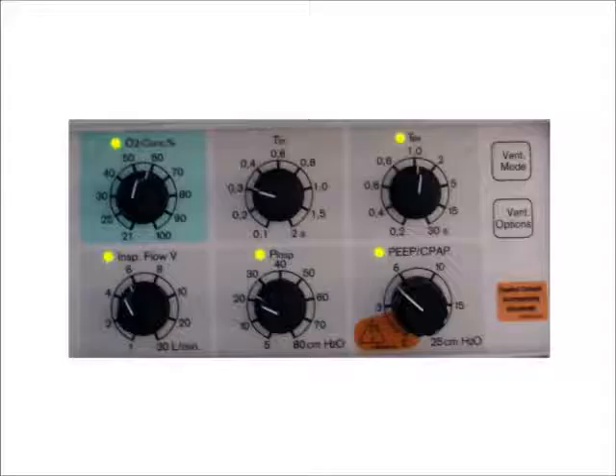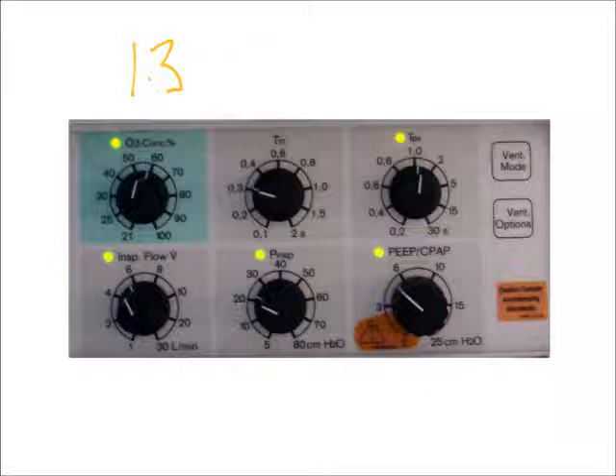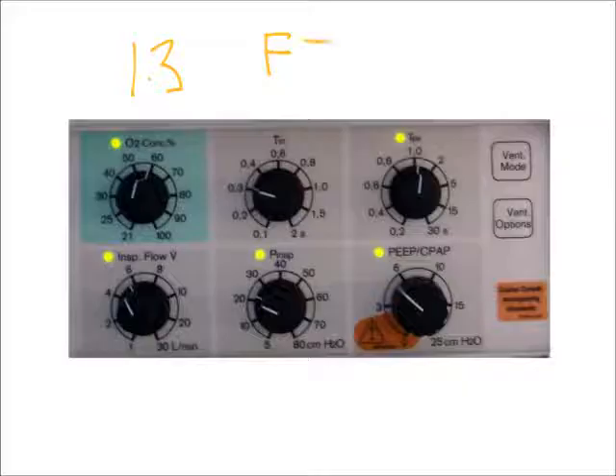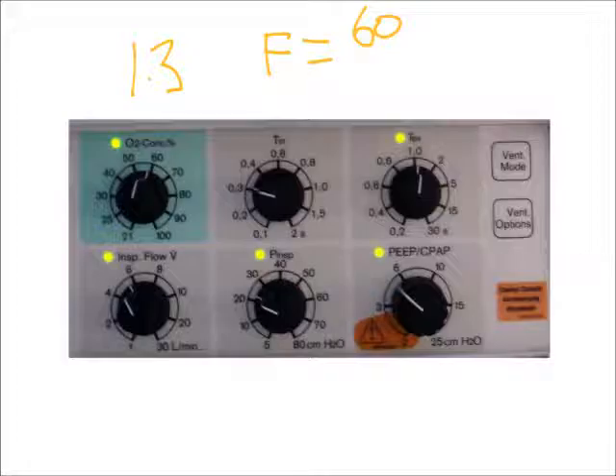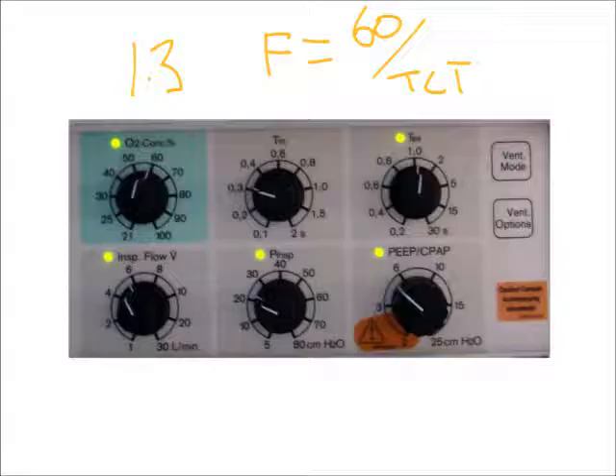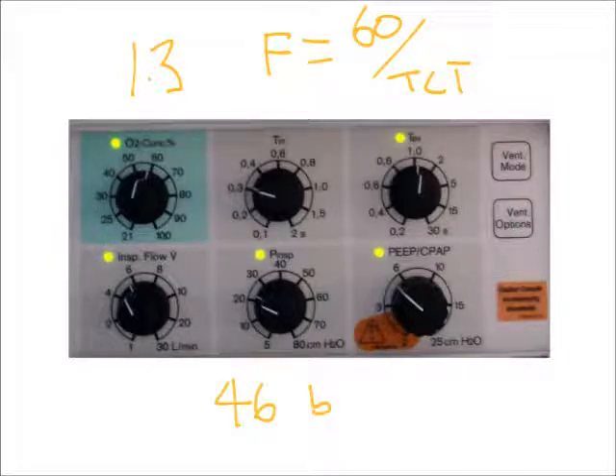Once you know your total cycle time, we had a total cycle time of 1.3 seconds, and we divide that into 60. That gives us our frequency. So our set frequency equals 60 seconds, because there's 60 seconds in a minute, divided by our total cycle time. If we do that, that's approximately 46 breaths per minute.